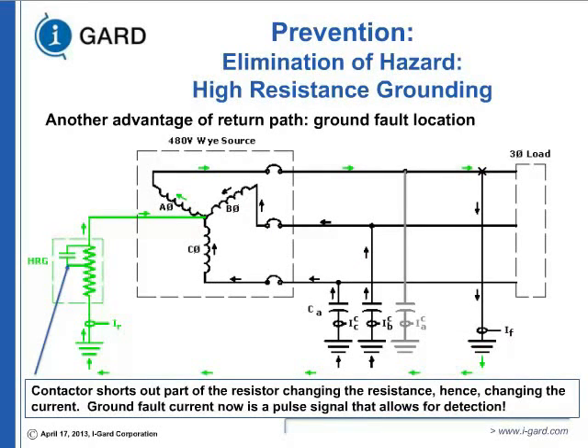So how do you eliminate that, and how would you detect that? It is ground fault location. One of the things that Delta cannot do is detect a fault. In this case, you have a contactor or some solid-state device that opens and closes 40 to 60 times a minute. So all you need is to find where that arcing current is flowing. Once you can do that, you're able to detect and isolate. If it's a quick fault, you can activate in 15 minutes or so and try to isolate the fault.